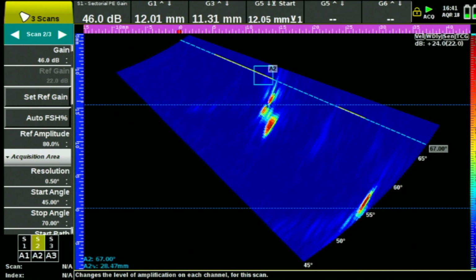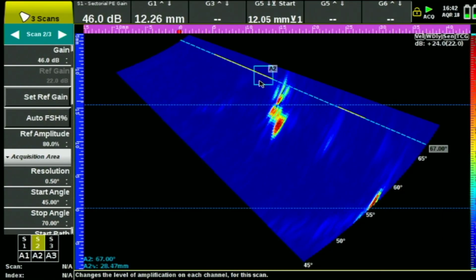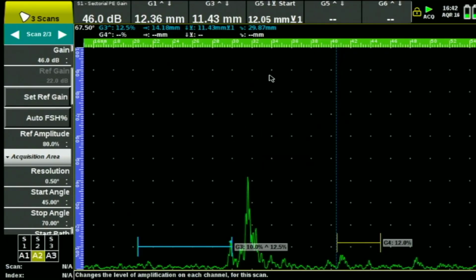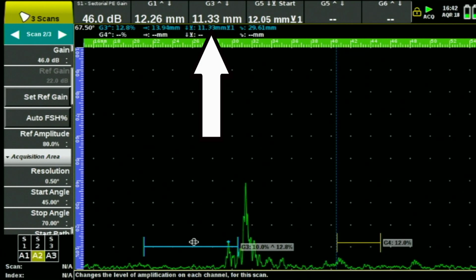So if we move the probe back and forth, you can see that as far as tip diffracted echoes go, there is some really faint ones right here at the top, right about there. I'm going to flip over to the A scan. Here it is there. It's coming in, that's gate 3 at 11.4 millimeters. So that's about 4.5 millimeter height. Compared to 4 millimeter height with the 16 element aperture, we're still pretty good.